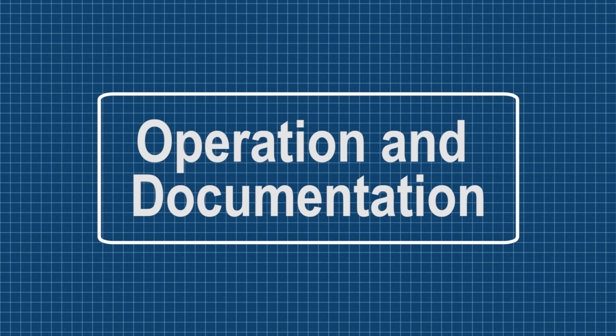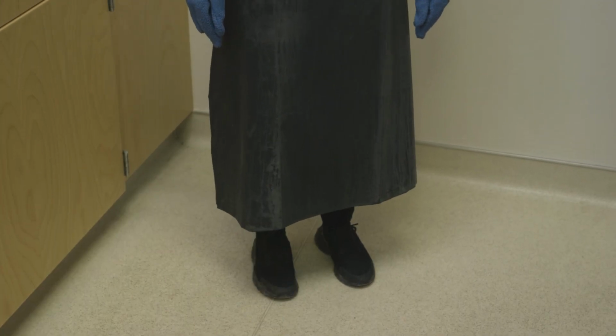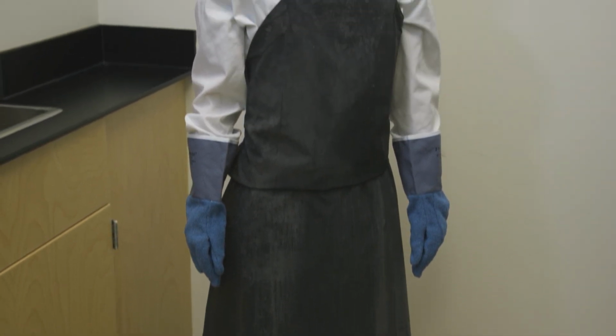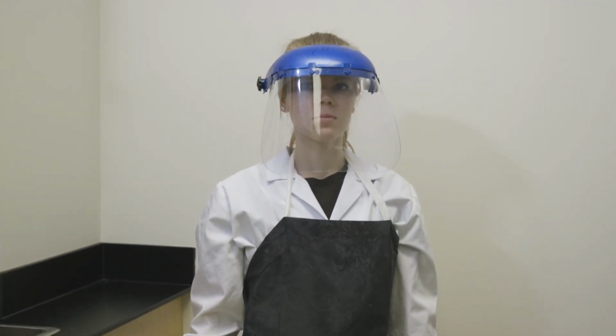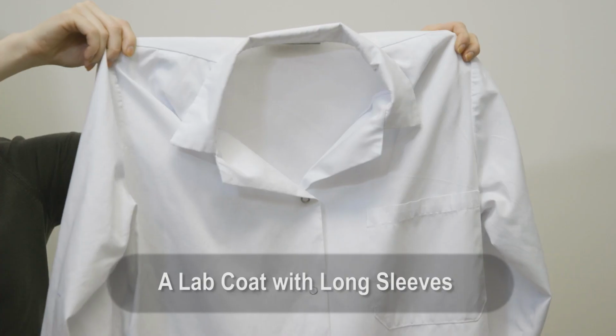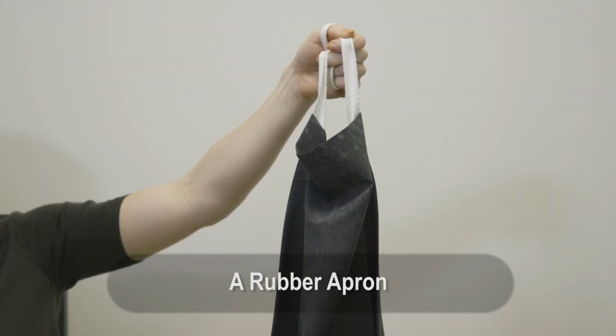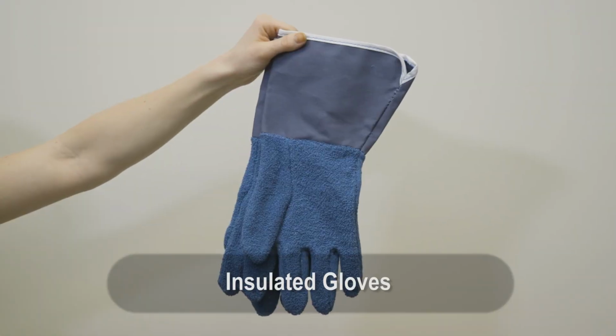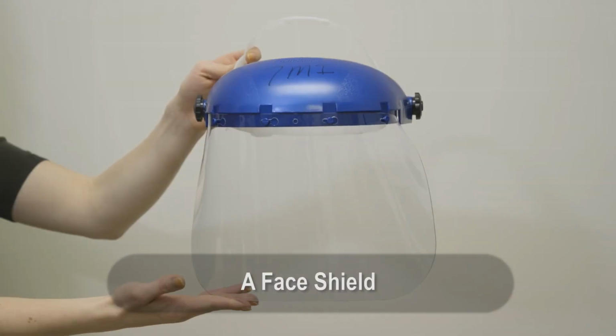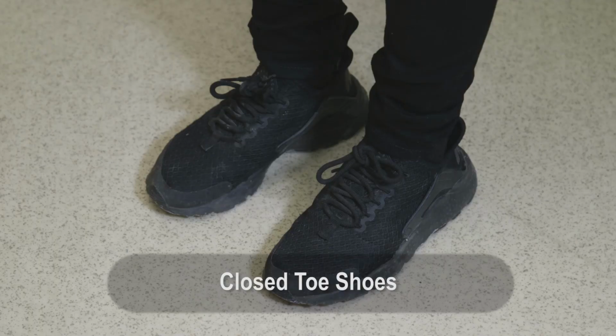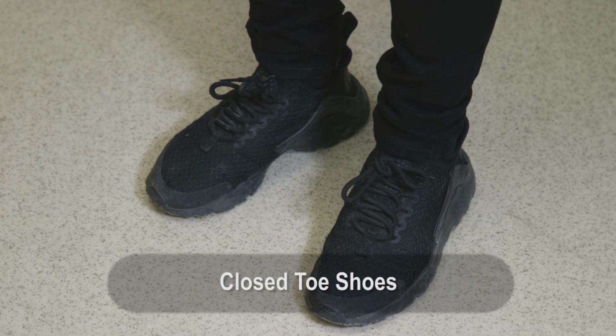Now that you're familiar with how an autoclave works, let's go into detail about how to properly operate and document the usage of your autoclave. For details about the specific usage of your department's autoclave, contact your supervisor for direction. The first step is to gather the proper safety equipment and clothing you will need during this process. Personal protective equipment, or PPE, includes a lab coat with long sleeves, a rubber apron, insulated gloves covering arms and forearms, a face shield for eye protection, closed-toed shoes that cover the entire top and sides of the foot, no ballet flats, and long pants.